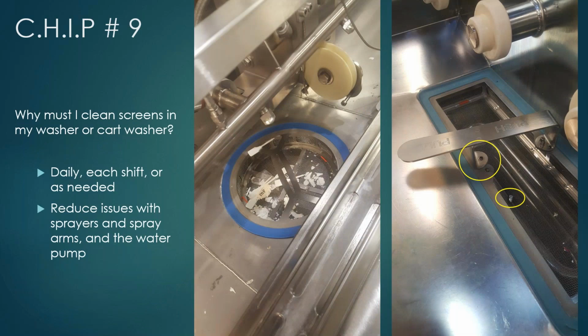Tip number 9, why must I clean the screens of my washers? Daily maintenance just cannot be overstated. It's there for a reason. It keeps the machine running well, and it produces better outcomes. When that machine is doing what it should be doing, you have better instruments produced on the other side. Especially the image on the left here rings true in a couple of ways.